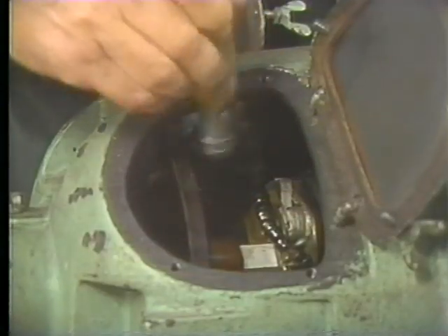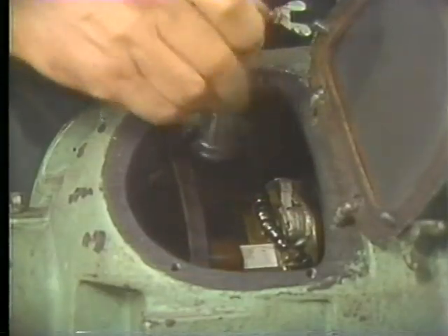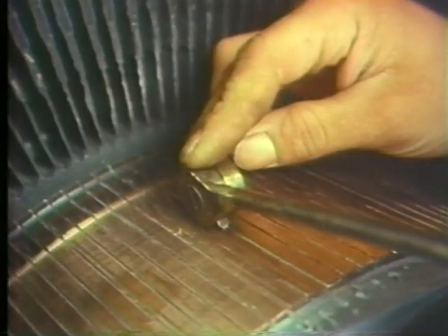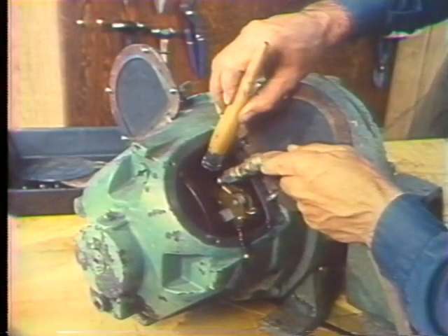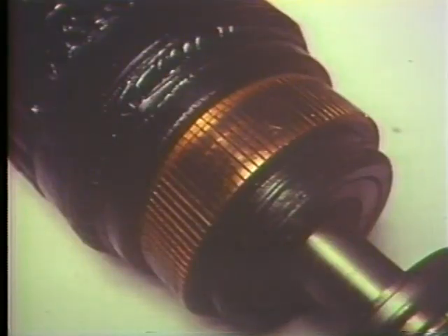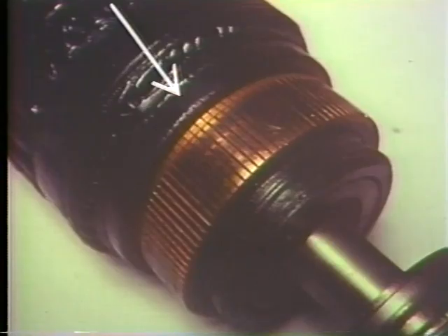Now, you can do a pretty good cleanup job with a soft brush. Most of the time, a hand slotter and scraper is used to remove any particles that get stuck between the bars. Dry air is good for cleaning away the debris between the segments. Before you put the brush and air hose away, there are two other areas you should check thoroughly: the bearing end of the commutator and the area behind the risers for carbon dust and dirt. These areas are susceptible to grounding.